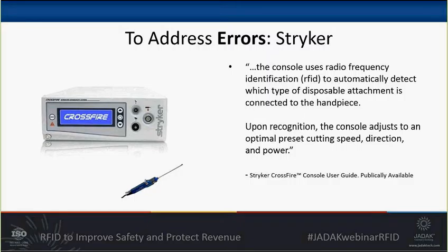These are shavers, or basically our disposables or consumables that are used, and each one requires a custom power setting from the console. Rather than having to manually reprogram the base station every time, Stryker added RFID. So this quote here is directly from the Crossfire user manual and says, "The console uses radio frequency identification to automatically detect which type of disposable attachment is connected to the handpiece. Upon recognition, the console adjusts to an optimal preset cutting speed, direction, and power."